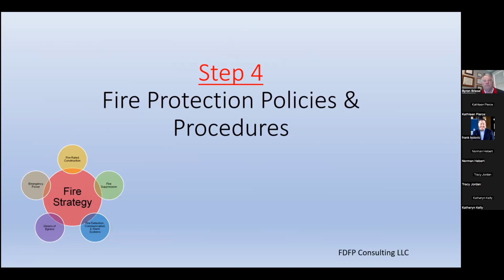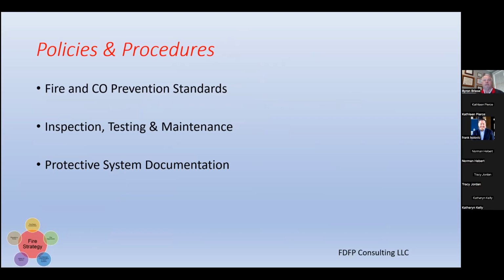Fire protection policies and procedures: you need them, they should be in writing, and they should be practiced. If they haven't come out of those books in a while, get them out. You need sound inspection, testing, and maintenance. And one of the most important things that I'm finding, as I still do reviews in hotels, is protection system documentation. That means the as-built for the fire alarm, the as-built for the sprinkler system, the as-built for the fire pump. You really need to be able to reach out and touch those. You may not have a dedicated fire command center in your building, but you should have an area prepared to operate as an emergency center, and this kind of documentation should be close at hand: the inspection, testing, and maintenance records, a basic drawing of the building, and then the protective system documentation. By the way, they're all deliverables under the code. If a contractor installed a fire alarm system or a sprinkler system in your building, that contractor was obligated under the code to give you accurate documentation. It's a deliverable.